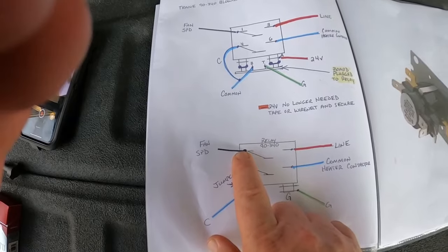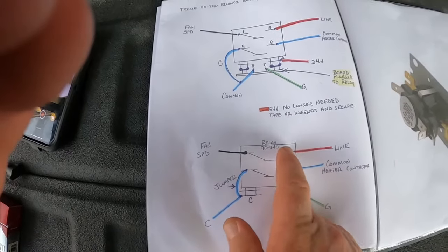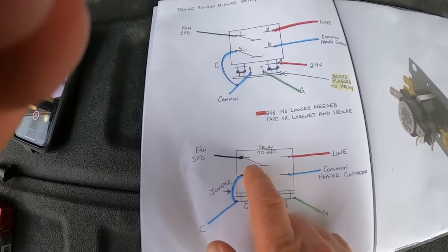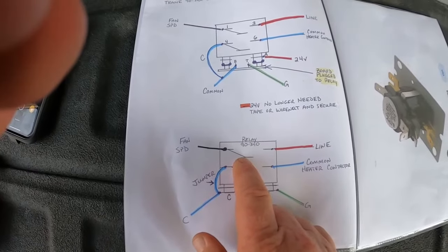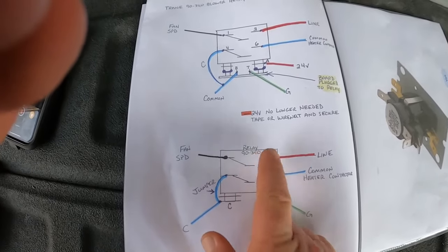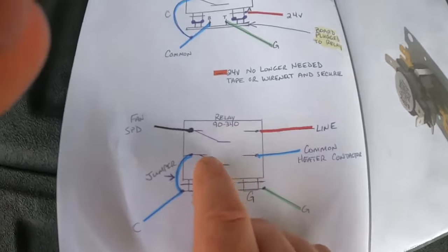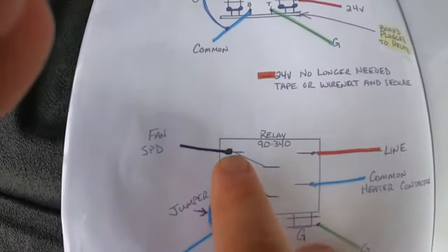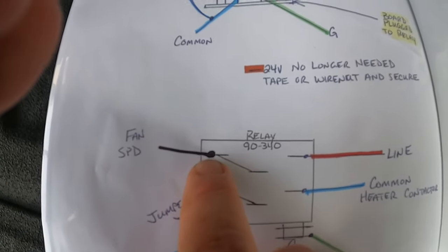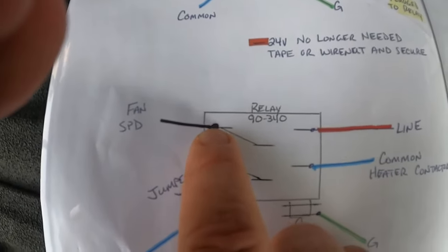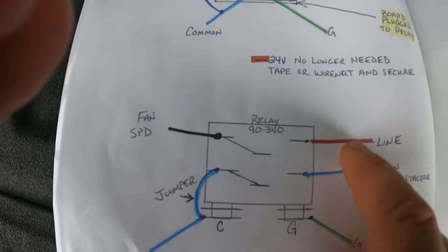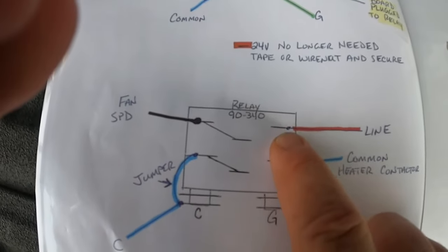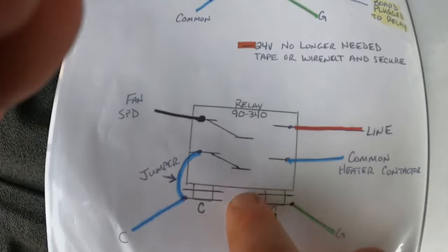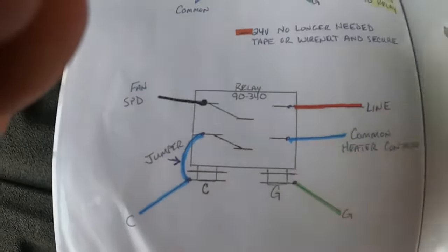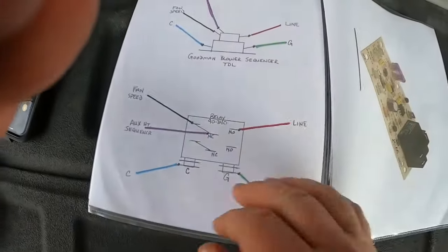Probably gonna have your line voltage in your heat strips backwards, normally closed. You put the breaker or the disconnect back and the blower comes on, you've ran your line voltage to the wrong place. And that's why I tell you, in all these scenarios, if you always put your blower speed off your blower motor on your top left common terminal, and you put your line voltage on your top right normally open terminal, you've already won half the battle. The rest of it is pretty simple to figure out.